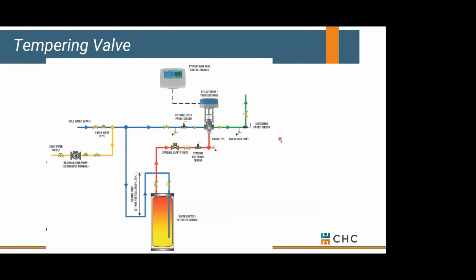Sorry, technical errors. So what we're calling here a tempering valve is a master mixing valve. Not point of use, but a master mixing valve in the mechanical room. And all this is doing is taking hot water that leaves our storage tank and blending it with city water, or our recirc water, to temper it down safely. So typically we're sending out 120, maybe 115, so nobody's getting scalded, but they still have hot water available.